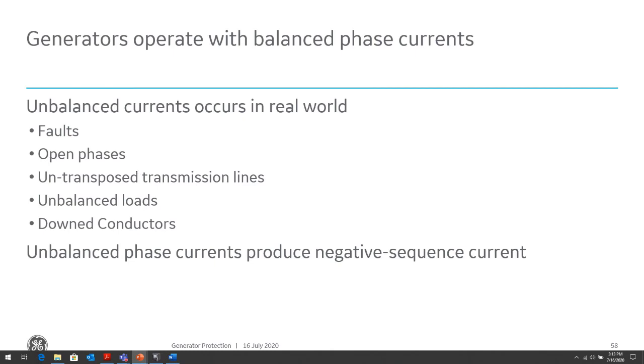The negative sequence currents rotate opposite the positive sequence, and they generate a 2 times current in the rotor. So say if it's a 60 hertz, it generates about 120 hertz current in the rotor. And that current will cause skin effects, and the current will flow into the rotor bar cross-sectional area where it's not meant to be, and again, heating in the rotor can occur, and over time, damage to the rotor. The rotor bar impedance increases and eventually is damaged.